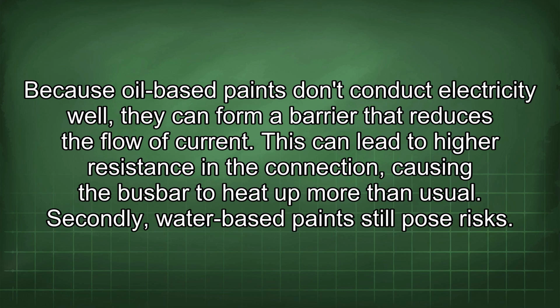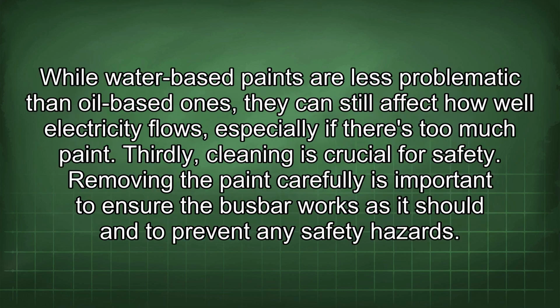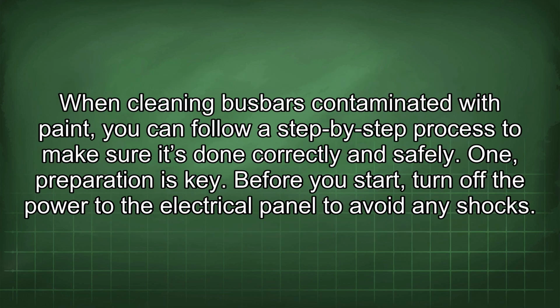Secondly, water-based paints still pose risks. While water-based paints are less problematic than oil-based ones, they can still affect how well electricity flows, especially if there's too much paint. Thirdly, cleaning is crucial for safety. Removing the paint carefully is important to ensure the busbar works as it should and to prevent any safety hazards. When cleaning busbars contaminated with paint, you can follow a step-by-step process to make sure it's done correctly and safely.